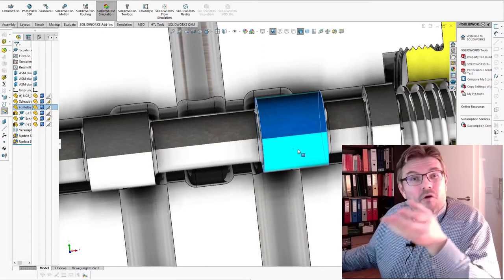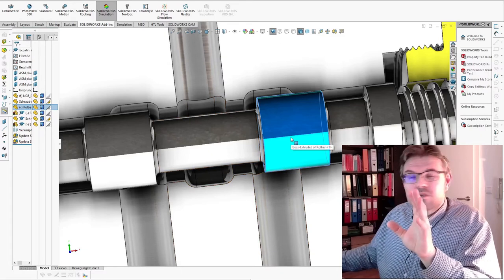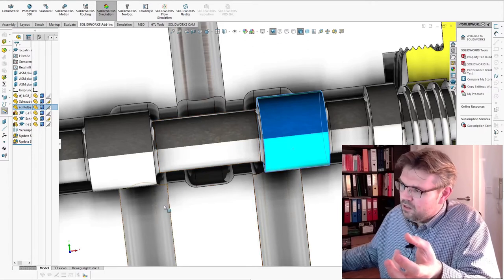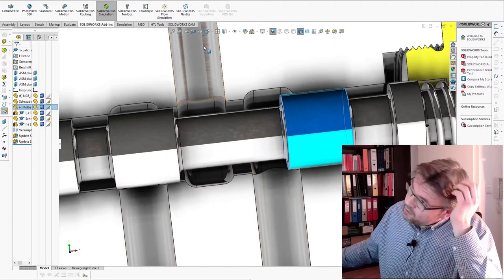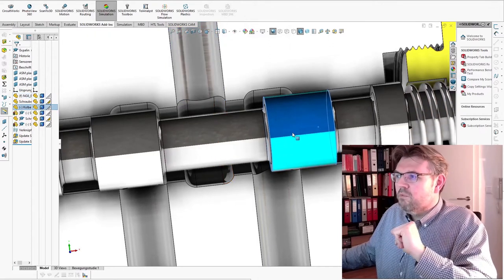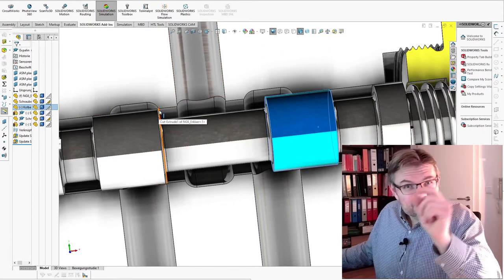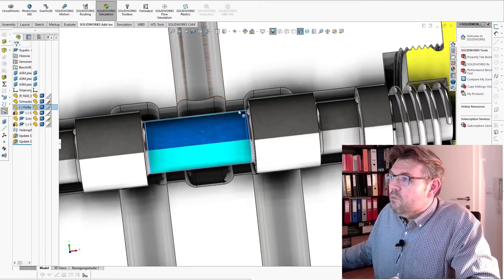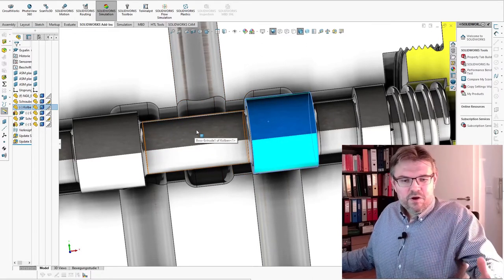There are reasons for this. So this here is smoothing, this is switching rather smooth. Here the pressure is dropping almost to zero. There will be a lot of pressure rush through the tank line and so on. However, now I have pressure on my working element here. Now the pressure is slowly decreasing, because here I have a tiny gap. This gap will get larger, so the pressure is dropping. And when we close the pressure line here, it drops even further. So the relief of the pressure is gentle.